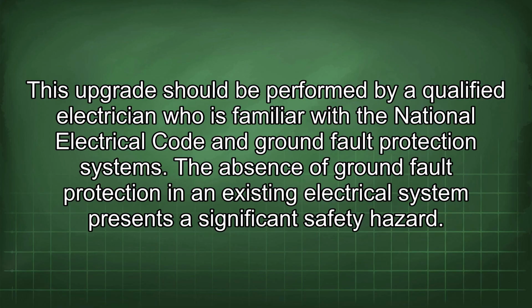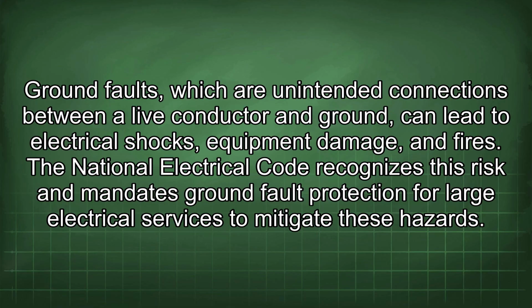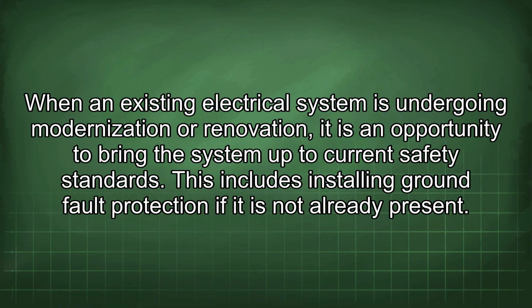The absence of ground fault protection in an existing electrical system presents a significant safety hazard. Ground faults, which are unintended connections between a live conductor and ground, can lead to electrical shocks, equipment damage, and fires. The National Electrical Code recognizes this risk and mandates ground fault protection for large electrical services to mitigate these hazards. When an existing electrical system is undergoing modernization or renovation, it is an opportunity to bring the system up to current safety standards. This includes installing ground fault protection if it is not already present.